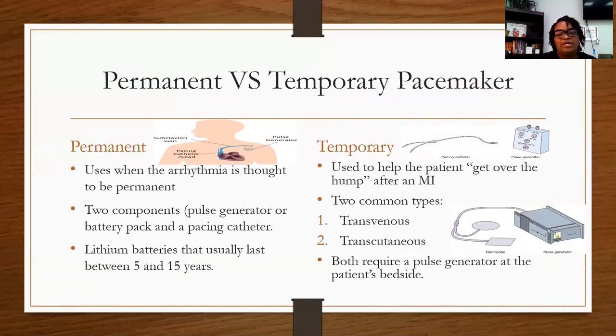So you have permanent pacemakers versus your temporary pacemaker. Your permanent pacemaker is used when the arrhythmia is thought to be permanent. There's two components. It has a pulse generator or battery pack and a pacing catheter. And it uses lithium batteries that usually last about 5 to 15 years. And your temporary pacemaker is used to help patients get over the hump, like after they've had a heart attack. There's two kinds. There's the transvenous and the transcutaneous. And both of these require a pulse generator at the patient's bedside. And here we see an example of these.